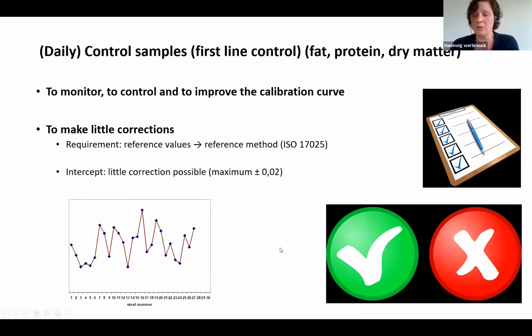Concerning the daily control samples, there are samples which can be used as first-line control. So with these samples, you can monitor and control the quality of the analysis daily. With these samples, corrections can also be made by changing the intercept a little bit higher or a little bit lower. However, there is an important requirement to do this. The reference value must be determined by using the reference methods. So never change the calibration curve based on results obtained by methods other than the reference methods.